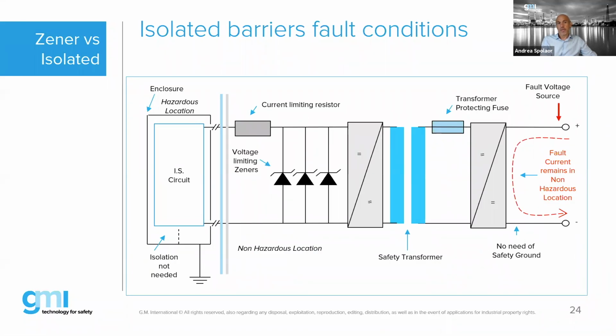In case of the isolated barriers, the sensor doesn't need any isolation from ground. The voltage fault will remain in the safe area, as you can see. Exactly, Andrea. These are the main differences between an isolated and a Zener barrier. There are several differences, but this is the most important.